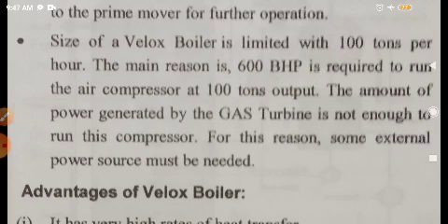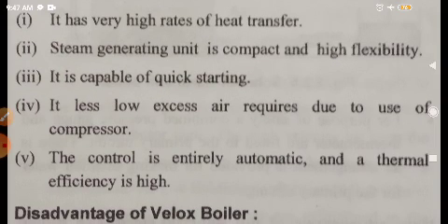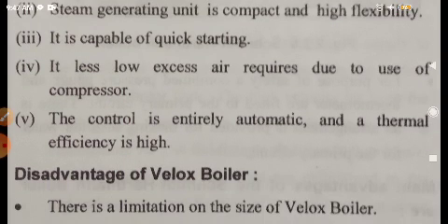Advantages of the Velox boiler: it has a very high rate of heat transfer. The steam generating unit is compact and highly flexible. It is capable of quick starting. It requires low excess air due to the use of a compressor. The control is entirely automatic and thermal efficiency is high. The only disadvantage of the Velox boiler is that there is a limitation on its size.